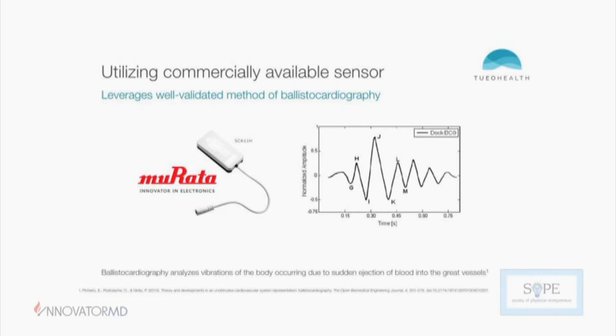The device we're using is an off-the-shelf device, and we're device agnostic, so we can use other devices. Right now, the one we have is made by Murata. They make accelerometers for the iPhone, and this is accelerometer-based technology. It goes on the mattress, so not a wearable, not something you have to put on. Measuring the small vibrations, you can get movement, so surrogates of sleep quality, but you also can get heart rate variability, respiratory rate, and other physiologic measures, all from the movements and from the scientific principle of ballistocardiography. So every time your heart's beating, there's a characteristic vibration.